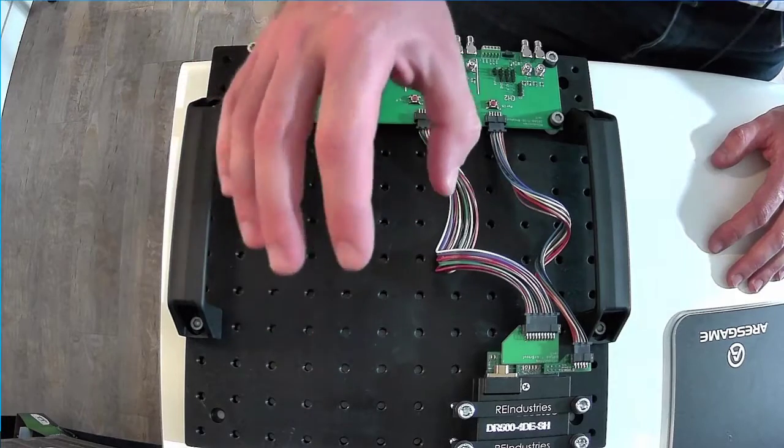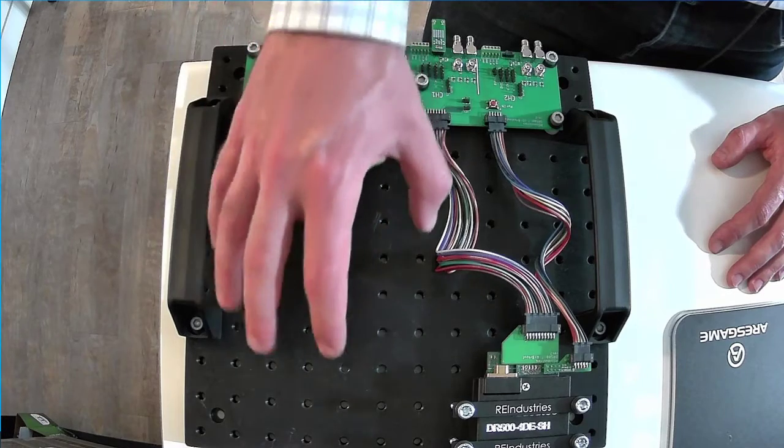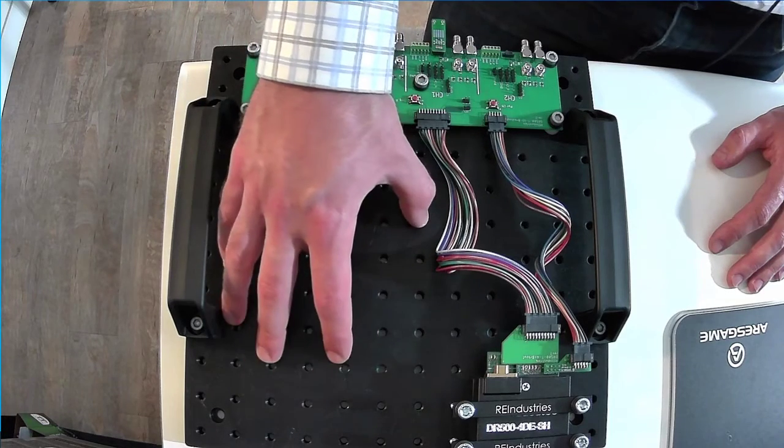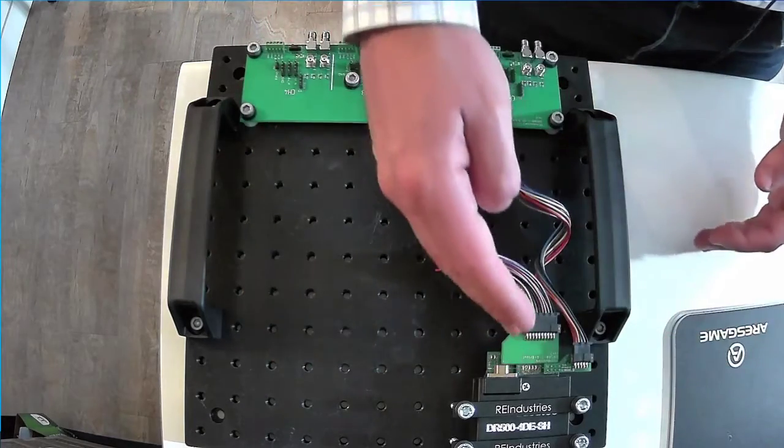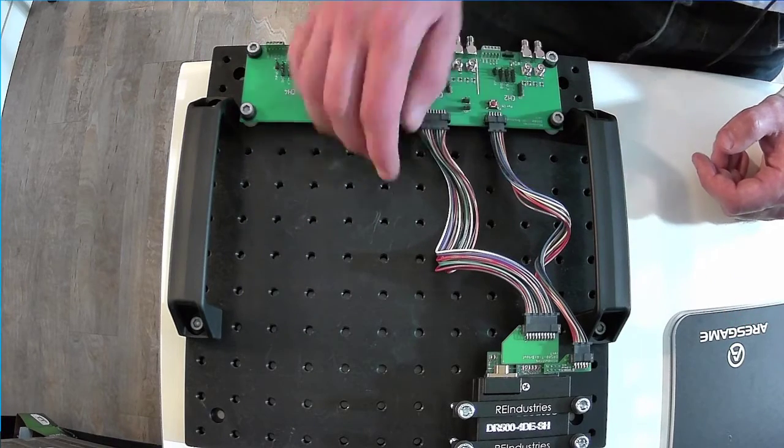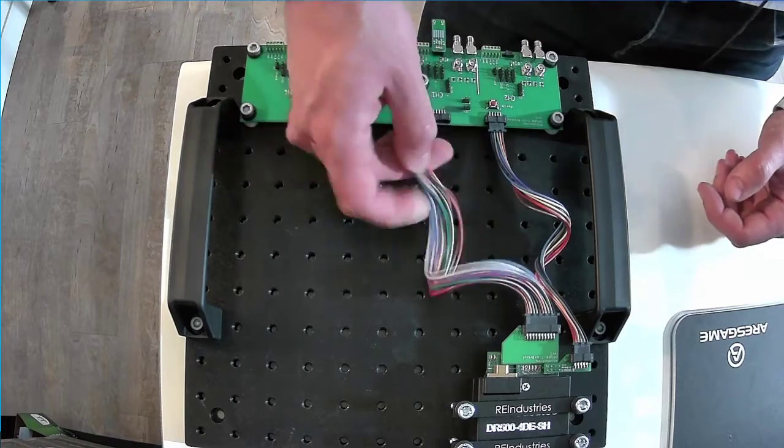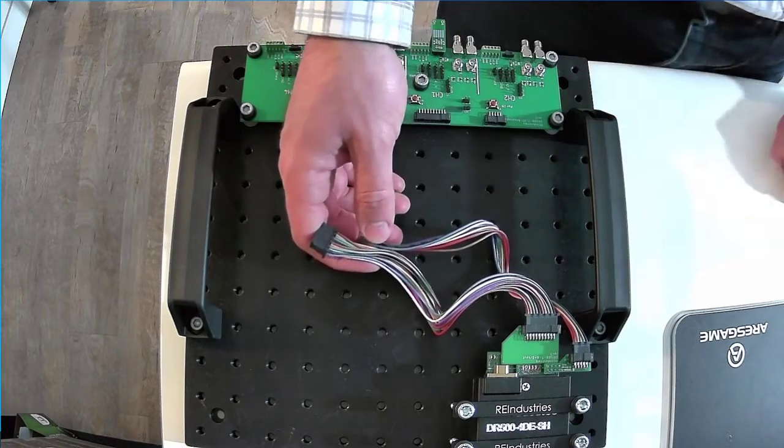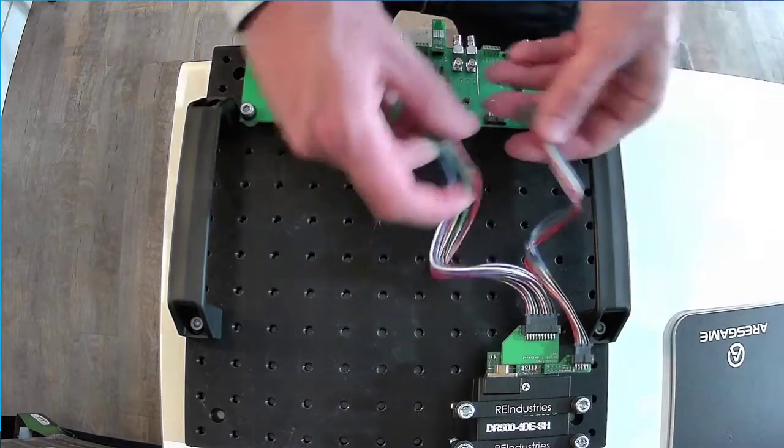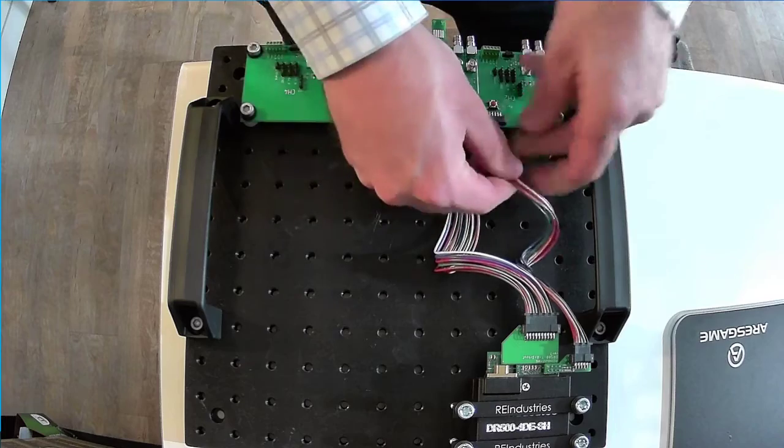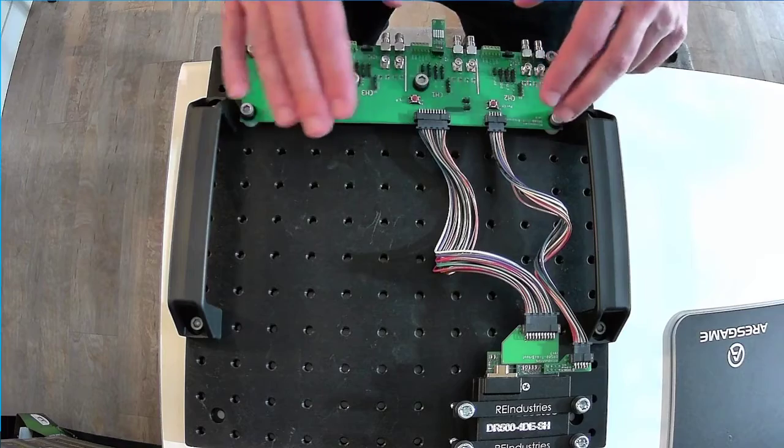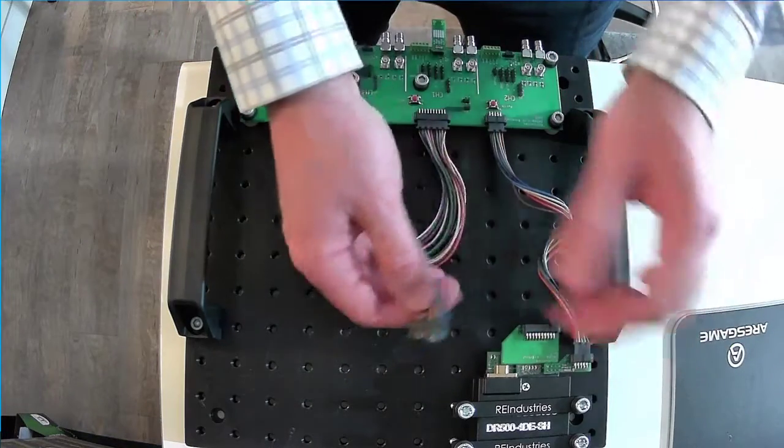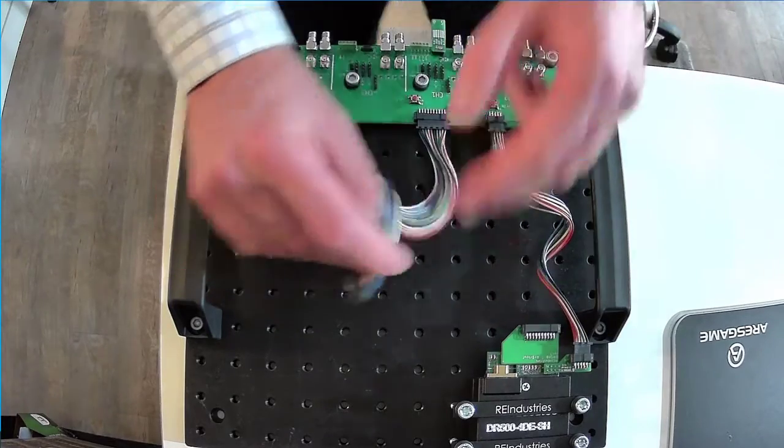And the other thing that's great, if there is any interest in adding custom customer electronics and PCBs here that you want to interface, either in the middle of this link or to one of these boards or to the recorder in a cleaner way, you can do that. Use the same connectors, all this information is available, the pinouts and the part numbers, and actually just pull these from our I.O. board and plug these in over here for your custom electronics application. So you can either go recorder into your custom board or you can interface your custom board to this I.O. board right here we have. So you can pull these out, remove the data recorder, and plug these into any custom hardware you might have.